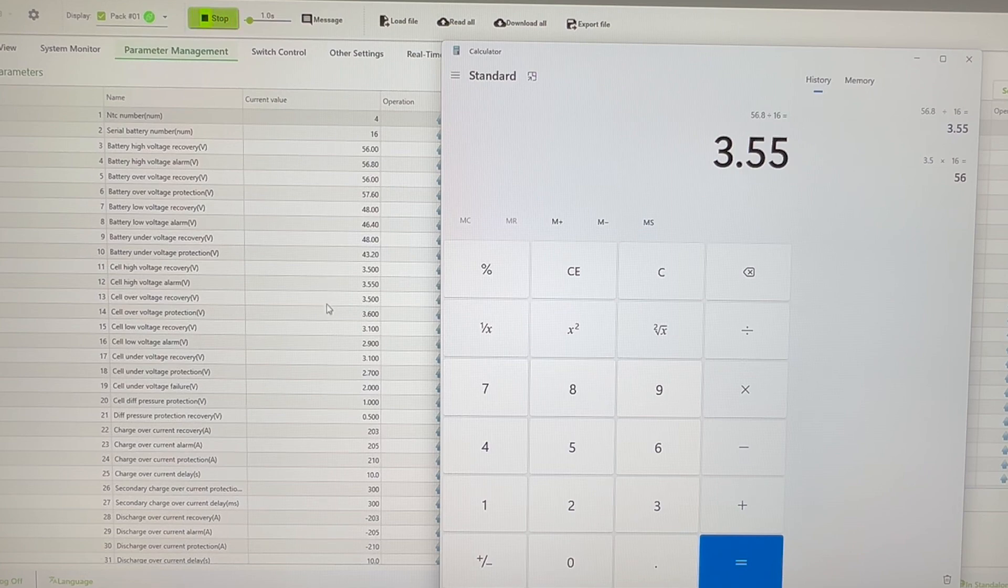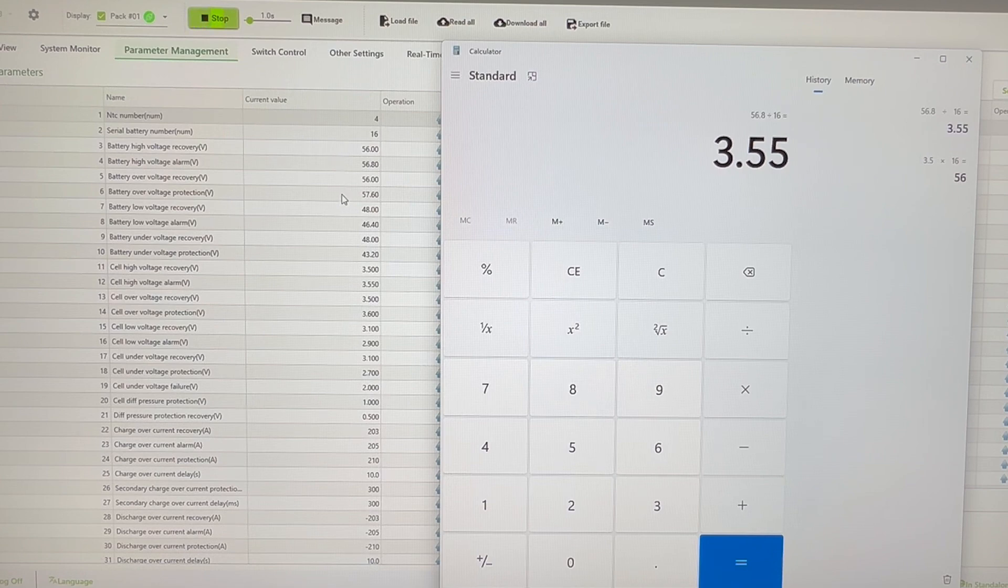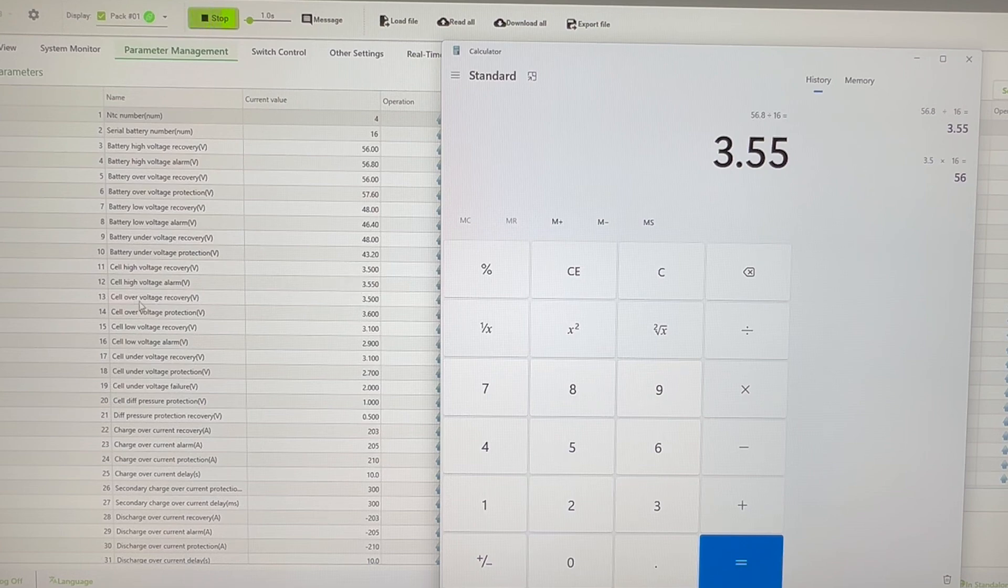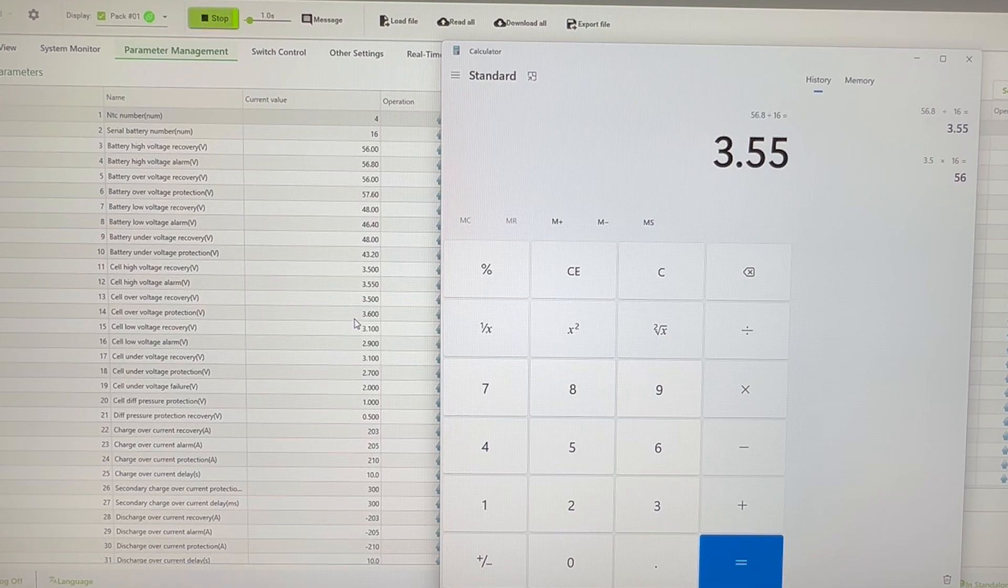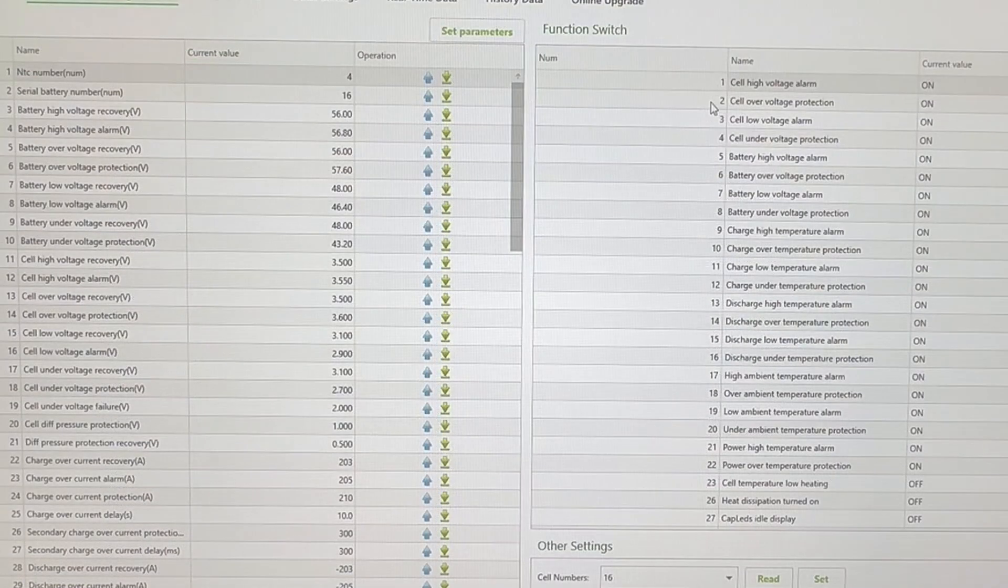So whatever your cell values are, you times those by 16. Whatever your pack values are, you divide those by 16, and all those figures are what you'll end up with there. So cell high voltage alarm 3.55, cell over voltage recovery 3.5, and cell over voltage protection is 3.6.